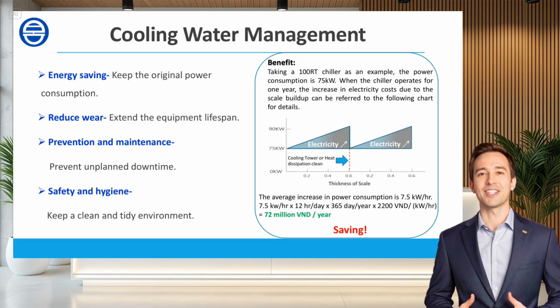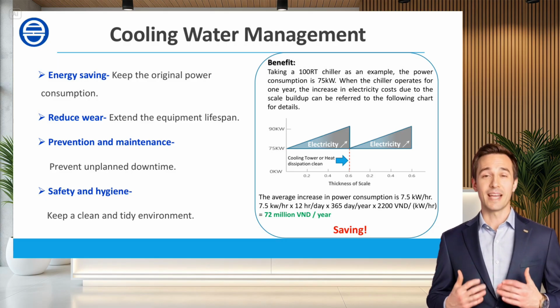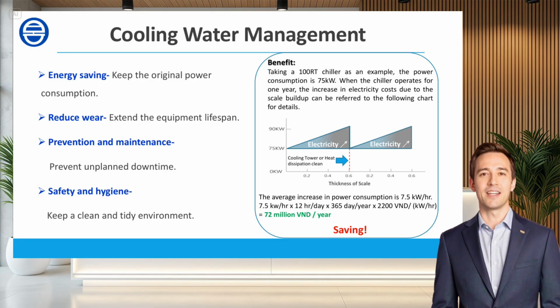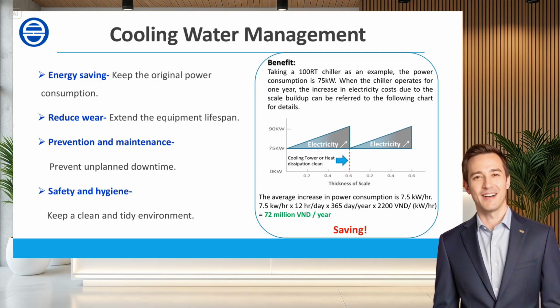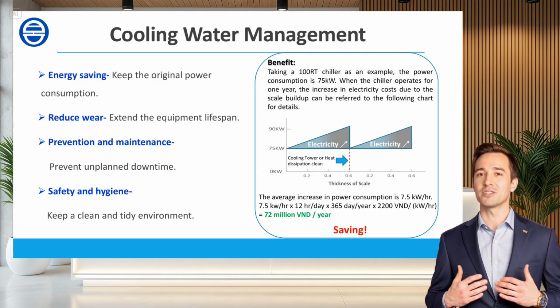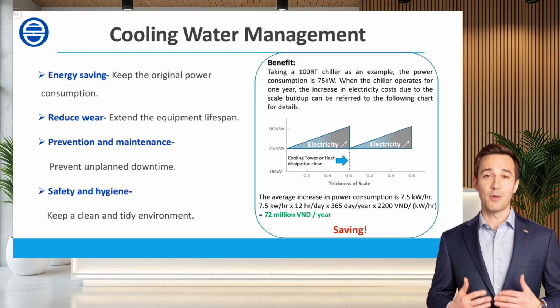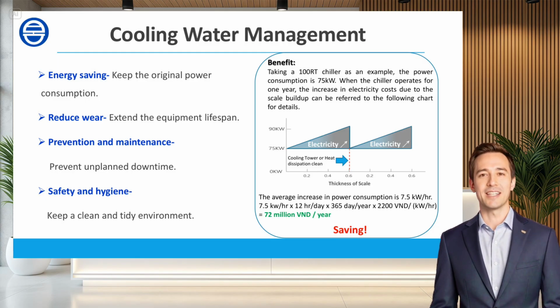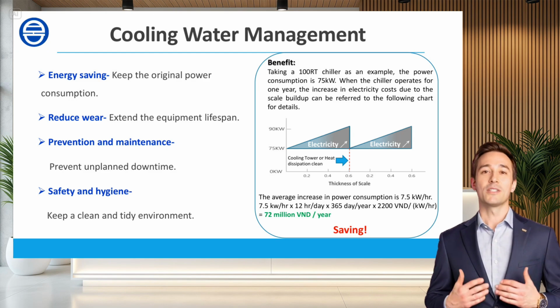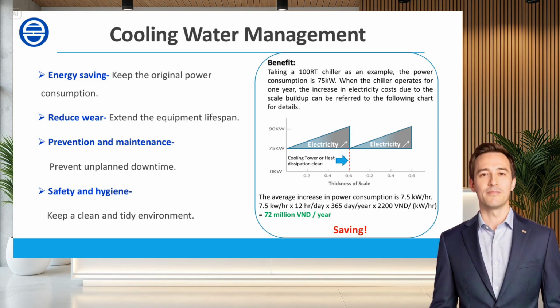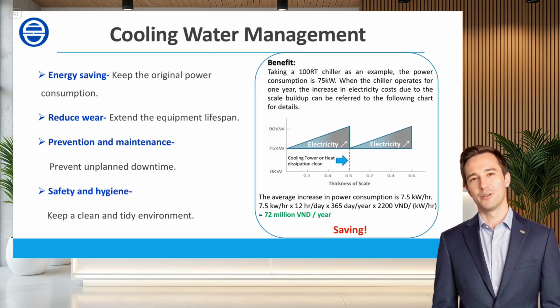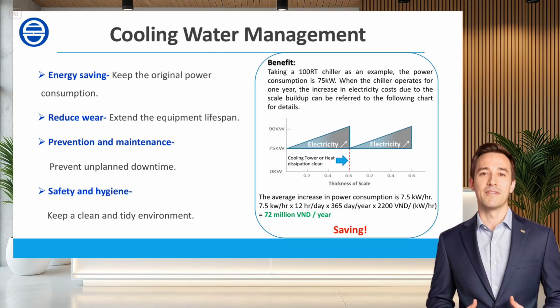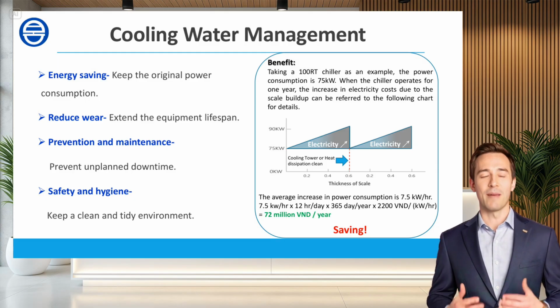Back to our 100-ton chiller example. Let's say it runs 12 hours a day, 365 days a year. With electricity at about 2,200 VND per kilowatt hour, keeping that machine clean and scale-free can save the company around 72 million VND per year on just one unit. So think about it. How many water-cooled machines in your factory have been secretly losing money year after year, covered in invisible layers of scale, the real energy vampires?